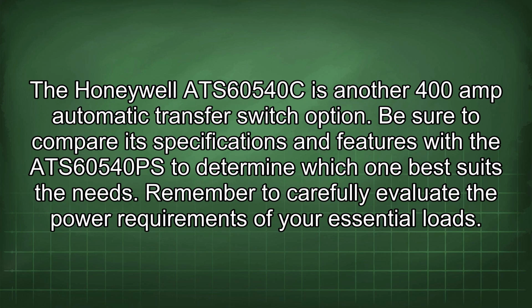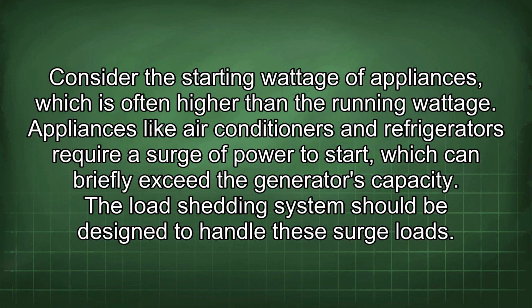The Honeywell ATS 60540C is another 400 amp automatic transfer switch option. Be sure to compare its specifications and features with the ATS 60540PS to determine which one best suits the needs. Remember to carefully evaluate the power requirements of your essential loads. Consider the starting wattage of appliances, which is often higher than the running wattage. Appliances like air conditioners and refrigerators require a surge of power to start, which can briefly exceed the generator's capacity. The load shedding system should be designed to handle these surge loads.